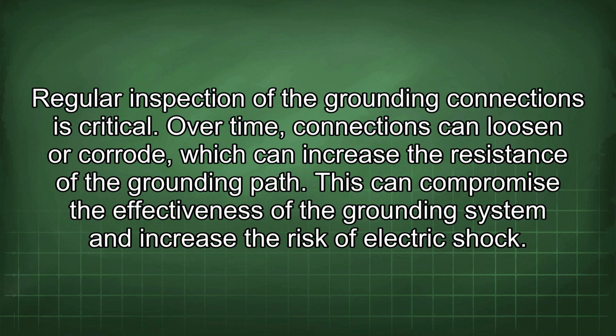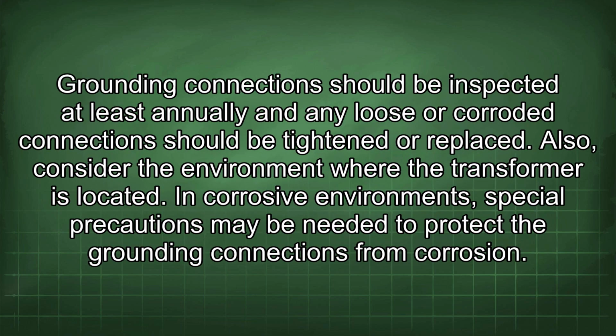Regular inspection of the grounding connections is critical. Over time, connections can loosen or corrode, which can increase the resistance of the grounding path. This can compromise the effectiveness of the grounding system and increase the risk of electric shock. Grounding connections should be inspected at least annually, and any loose or corroded connections should be tightened or replaced.